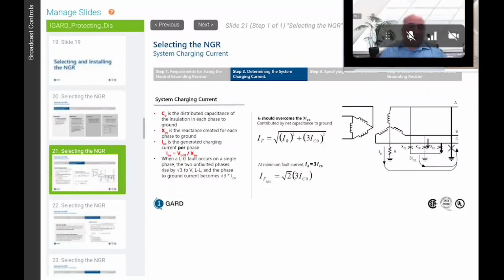So we go to the charging current again. Typically, you can determine what the charging current is on your system by doing several things. You can measure the current at the ground fault and vectorially subtract the current going back through the resistor, and you can figure it out with this relationship. So the fault current at point A, at A phase, is equal to the square root of I_R squared, which is the current going through the resistor, plus (3I_C0) squared, which is your charging current.